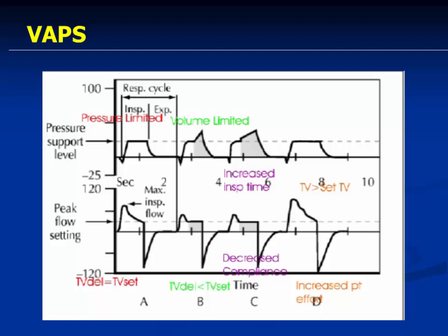The settings have changed. And over a period of time, you can compare, there is an increase in inspiratory time as well. So the ventilator, this microprocessor, has calculated that with this much duration, I cannot deliver this much tidal volume. So it has increased inspiratory time to deliver that much tidal volume. And by changing the flow pattern, as you can see here, the flow pattern has also changed. Suddenly the flow has become high.